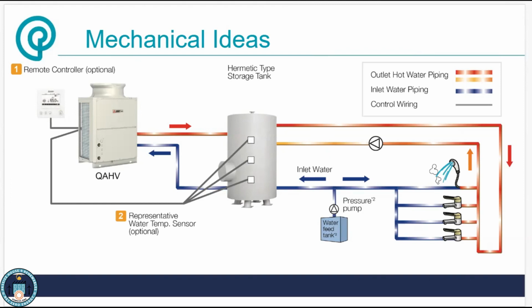Question: did you look at traditional solar hot water for multifamily, less complicated, more efficient, and not using refrigerant? We don't see a whole lot of it on our projects. I understand it's highly efficient and a great way to preheat water, but the issue is you have to have a lot of storage so you have hot water ready when you need it. It could work well if you're trying to keep a lot of hot water in a tank, and then you've still got some kind of post heater to make sure you're hitting that set point.